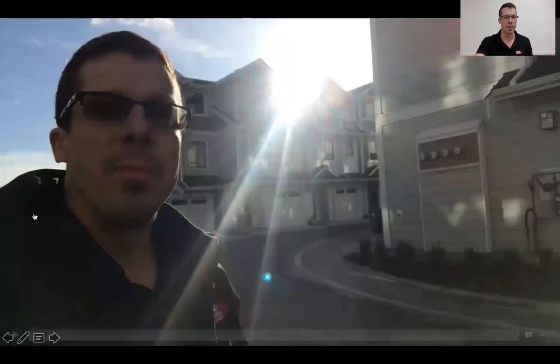The city inspectors are saying that if the house has sprinklers, which it did, then the garage door does not need to be a fire rated door, which, okay, I'm okay with that. But it still needs to be self-closing to prevent the fumes from going in there. And it still needs to have a weather strip so that the smoke or the fumes from the car don't get inside the house. So, okay, you passed it based on one item. There's still 2 deficiencies with that door. So anyway, it is what it is.